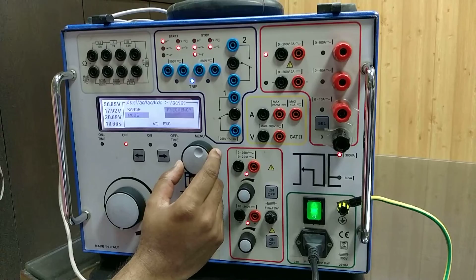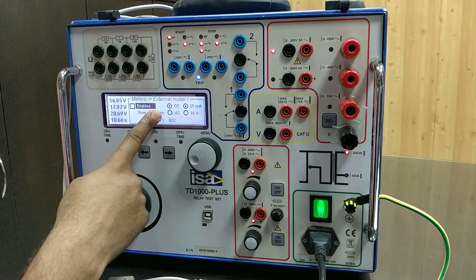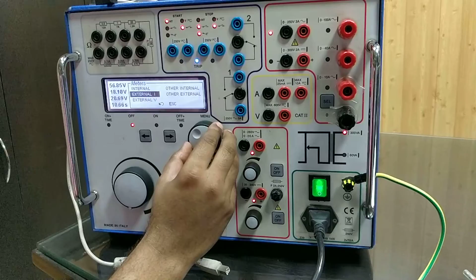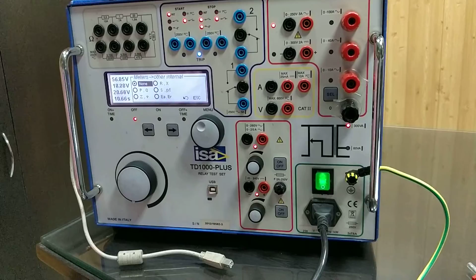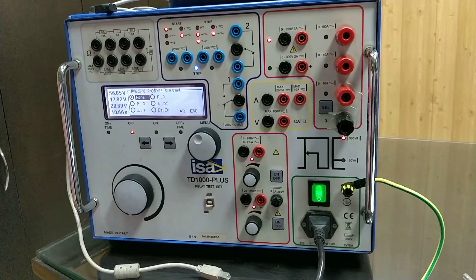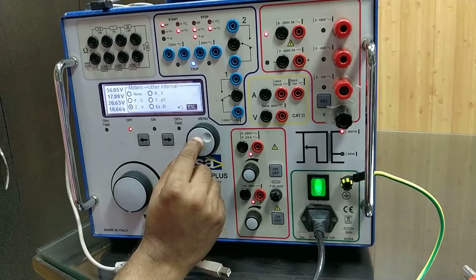The kit also has options like measurement. In the measurement, we can have an internal measurement which is already showing on the display. Apart from this, we can select the external current measurement or external voltage inputs. Inside the external current input, we also have options like selection of AC or DC signal as well as a range. It is also capable of displaying the outputs in different functions, like for example impedance and phase angle, and this we can see on the screen.